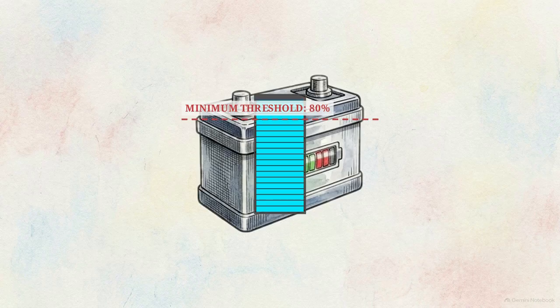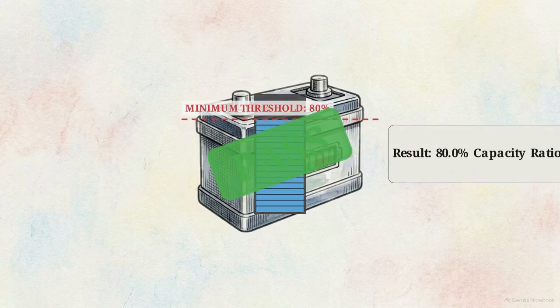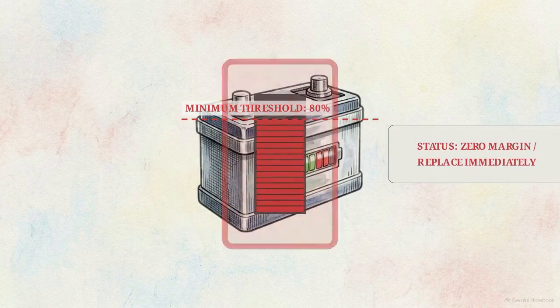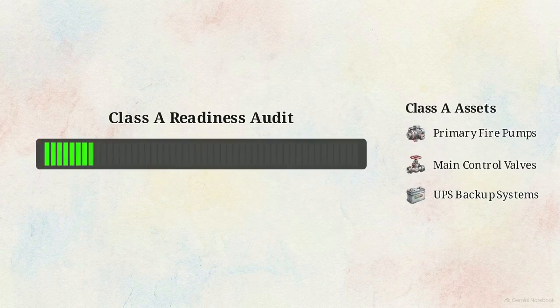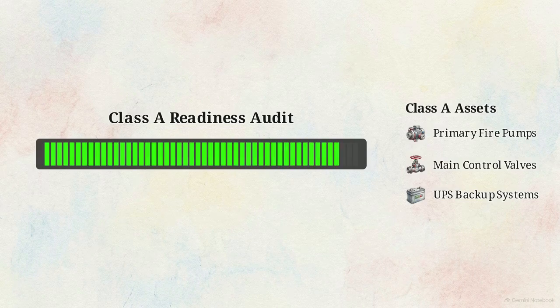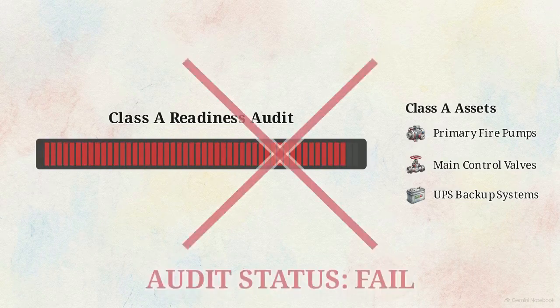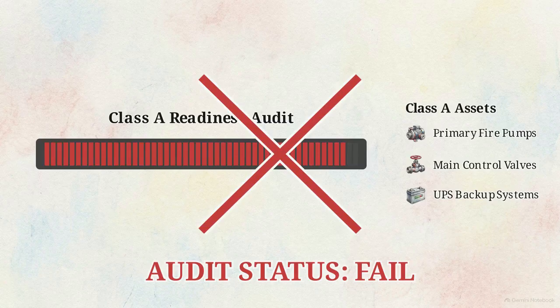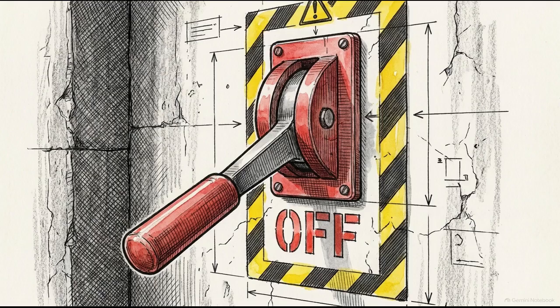We see the same zero-margin state in backup power. If a battery test delivers exactly 80% of its baseline, it technically passes, but 80% is the absolute minimum threshold for replacement. To maintain the Tier 4 standard, facilities use a 100% critical gate. If a single Class A asset remains offline or critically degraded, the entire facility fails its readiness audit. Readiness is a binary state. If you cannot prove 100% capability on your critical path, you have 0% protection.